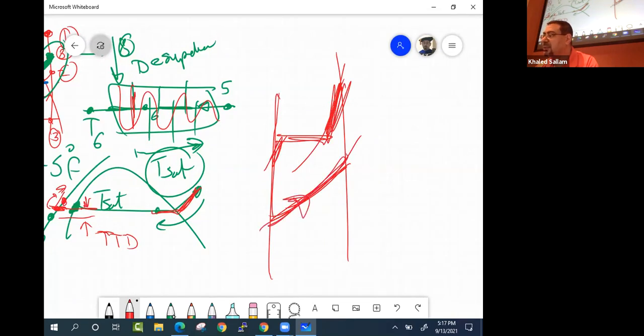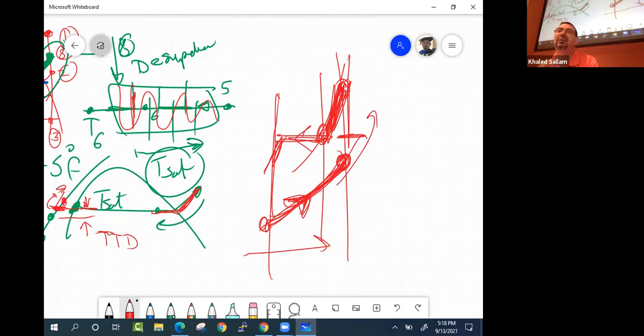this, or the feed water. So while the feed water is trying to heat, it's going in counterflow arrangement with the steam that is doing this. So in that part, and we call this part the desuperheater, very hot steam is used to heat the water. So the water not only can reach this point, the water can even go a little bit higher.